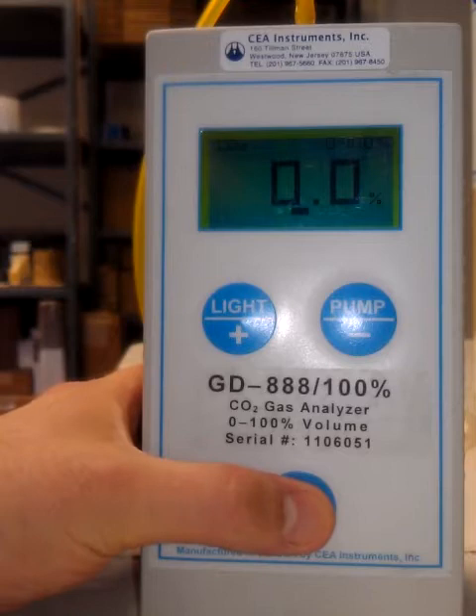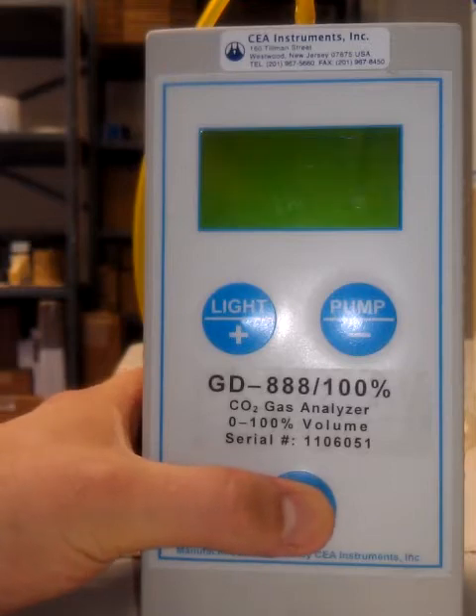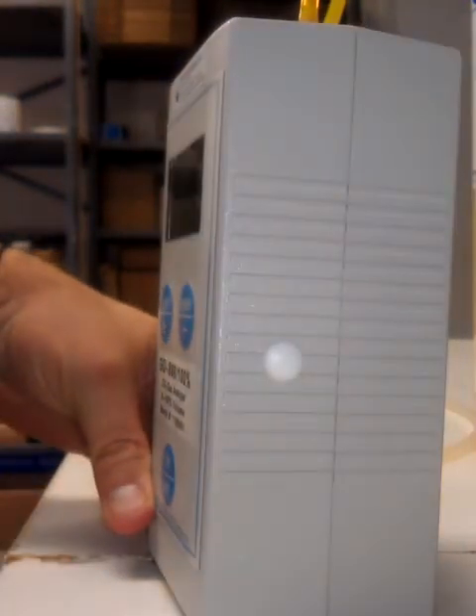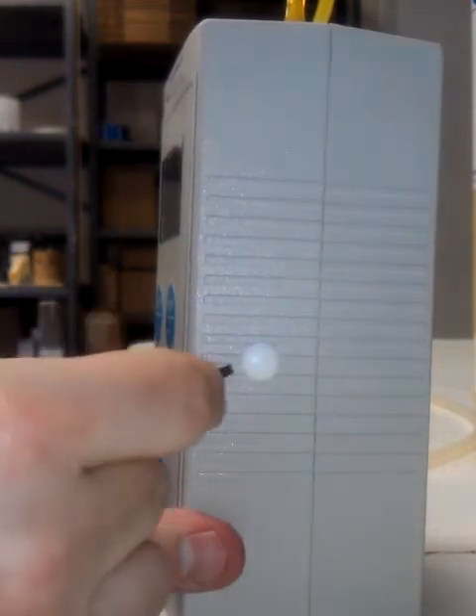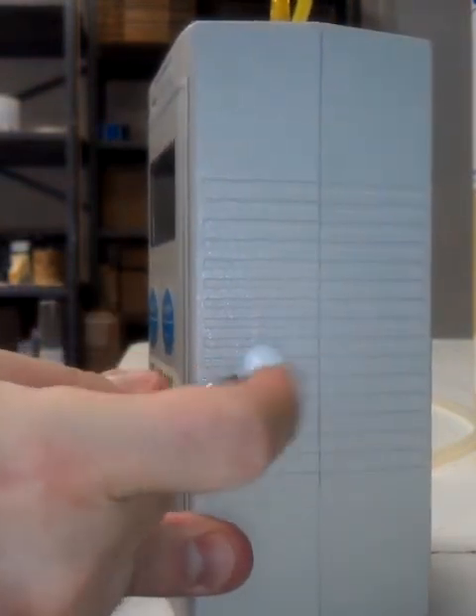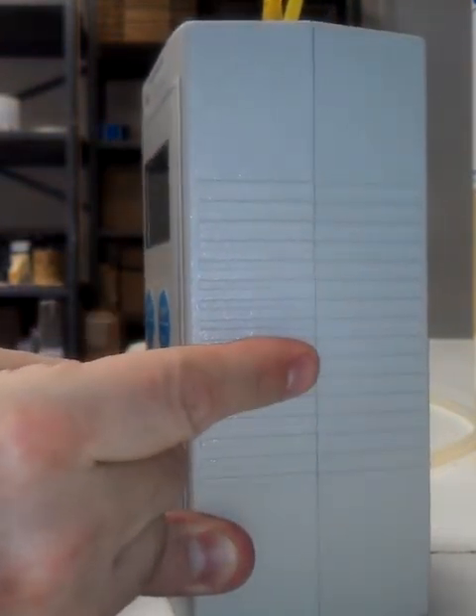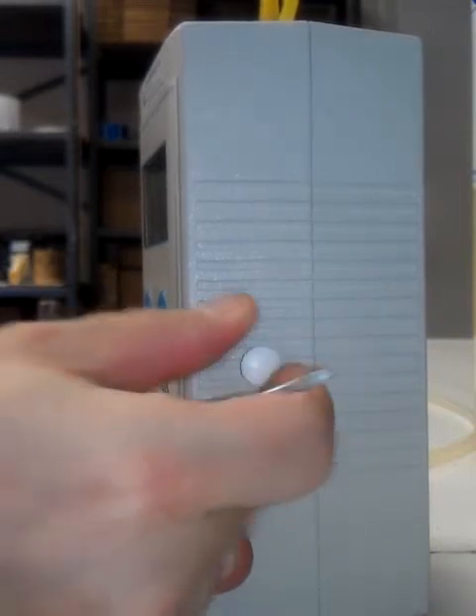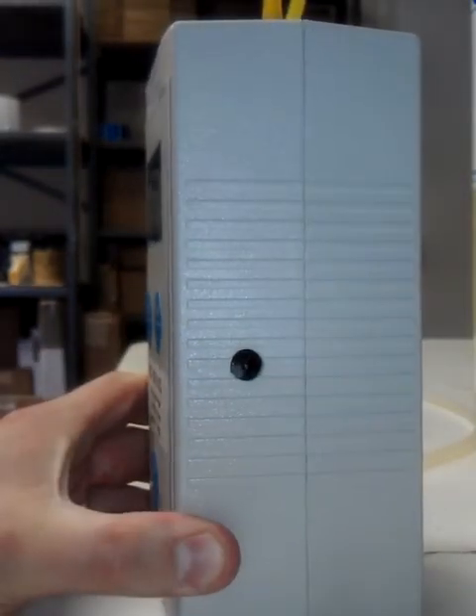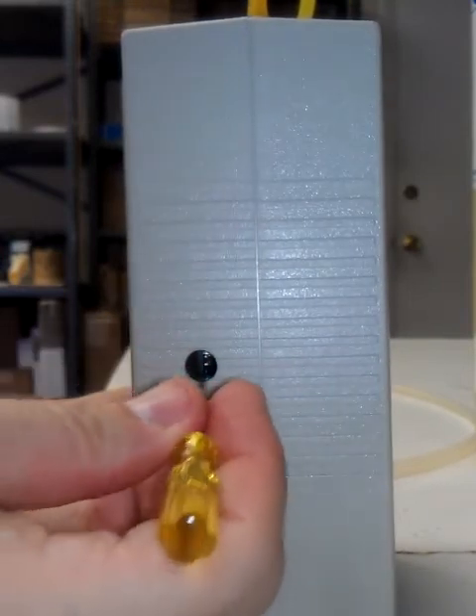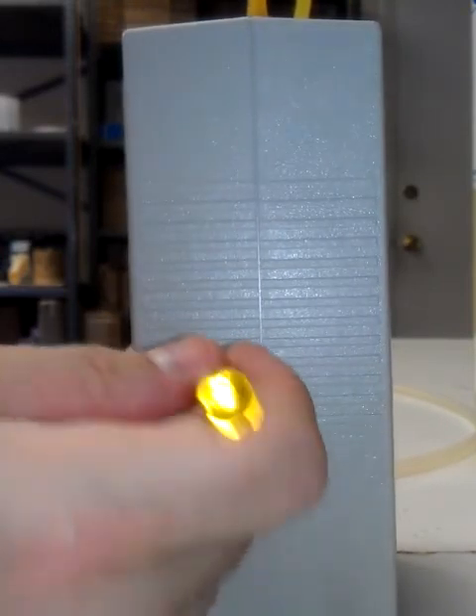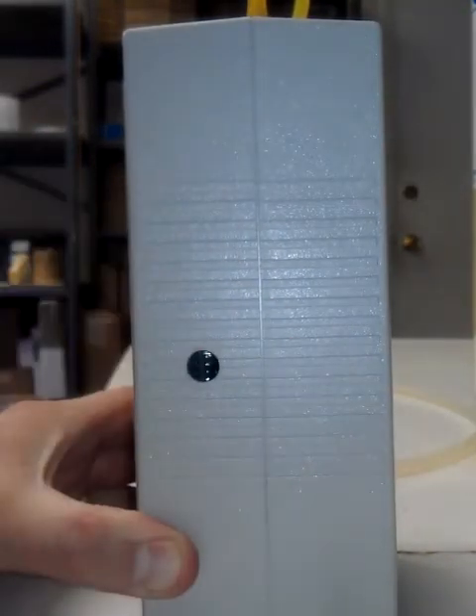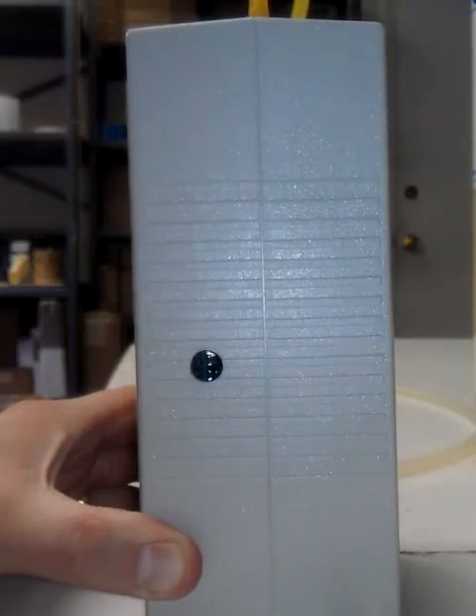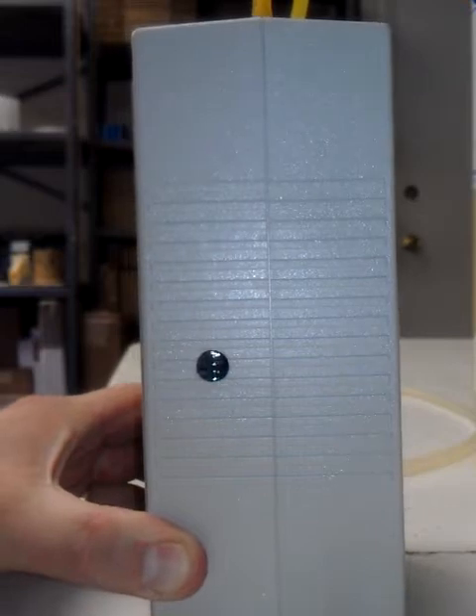The unit needs to be off. On the side is a little protective cap. You can take the cap off, and it should always be on, and don't touch anything unless you must perform a calibration. And there is a hole, and there's a little switch that goes up or down. Down changes the alarm set, but on the fire suppression units, we usually have the alarm all the way up, so you should not do that.